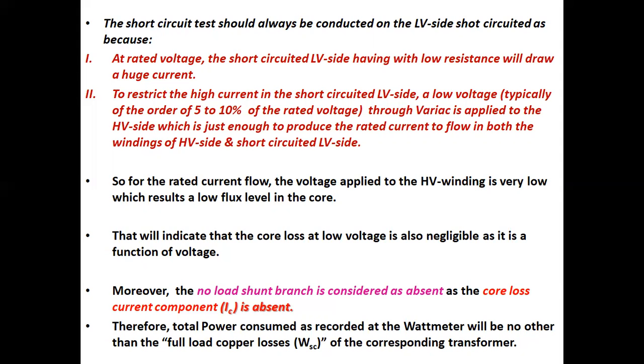So for the rated current flow, the voltage applied to the HV winding is very low, which results in a low flux level in the core.